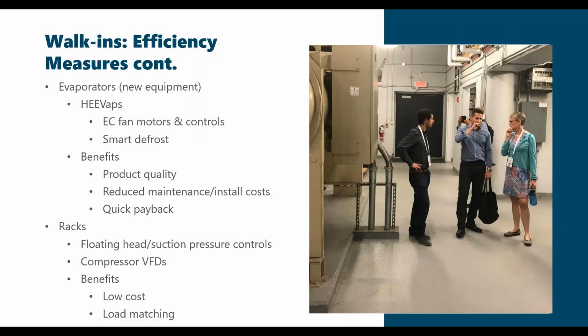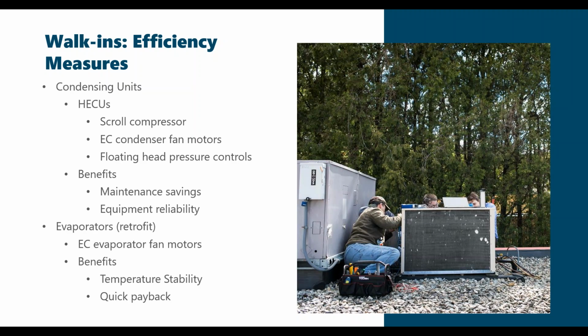So now moving on to the low pressure side. Oops, can we go back just one moment, Zoe, and talk about the evaporators. So this is on the low pressure side contained in the walk-in. So it can have 2 to 6 fans and replacing out the evaporator fan motors. So upgrading from shaded pole or permanent split capacitor to ECM, so the electronically commutated motors, or in walk-ins, we've seen a lot of success with Q-synchronous motors. And there's about 60% energy savings here. And it's a really easy measure for customers to start with. So this would be a good place for a retrofit.